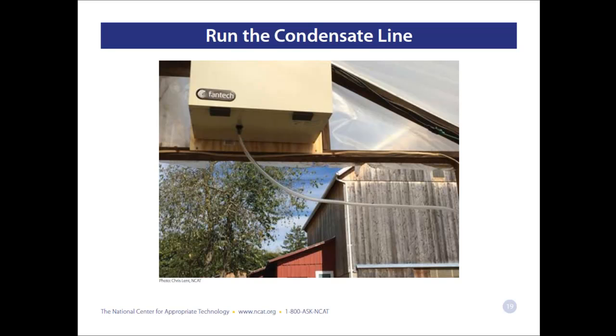So for this project, we set the unit to shut off at lower temperatures. Anytime it got below 35 degrees in the high tunnel, the unit would not run, so there would be no condensate to deal with. I think that if it could run without freezing at lower temperatures, it would have done a lot more running. If we'd allowed it to do that, it might have impacted the results of this project to have the heat recovery ventilator running at lower temperatures. But as it was, we wanted to avoid that problem of freezing condensate, so we had it shut down under 35 degrees.